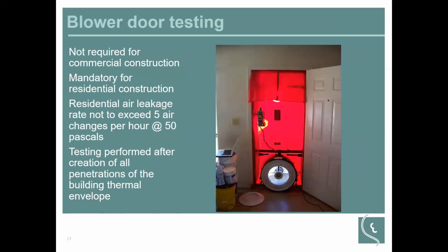So here we have a blower door. And this instrument depressurizes a facility. That fan is blowing air to the outside, and it's depressurizing the interior. And it's a very effective way of identifying where the air leaks are and also the quantity of those air leaks, because it measures how much air is moving through that fan.